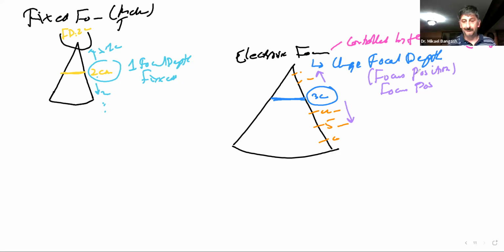But no matter what, if it started as being focused at this point, the system is just run so that the beam is at its narrowest at this depth. Let's say you change the focal position to a greater depth. Let's say to a depth of 4 centimeters rather than 3 centimeters. That may mean that now the beam is focused at this depth.